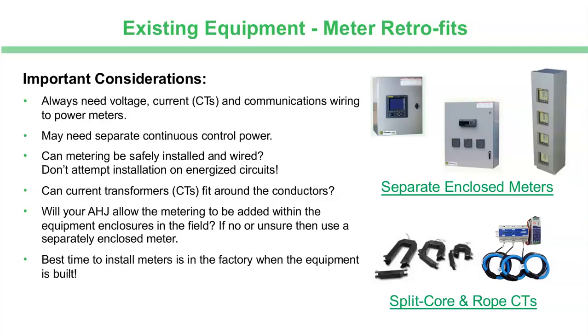A quick note on safety. Whenever you're dealing with metering being retrofit, it is strongly advised, if not insisted upon, that those be on de-energized circuits. And I know in healthcare that's always a challenge. That's why you should always try to incorporate it in your brand new equipment. But where you are retrofitting, please be very cautious of energized circuits. Whenever you have current transformers, be sure that you have shorting blocks installed for those. So in the future, if you do need to service that meter or any of the circuits inside, you have a way to safely do that.